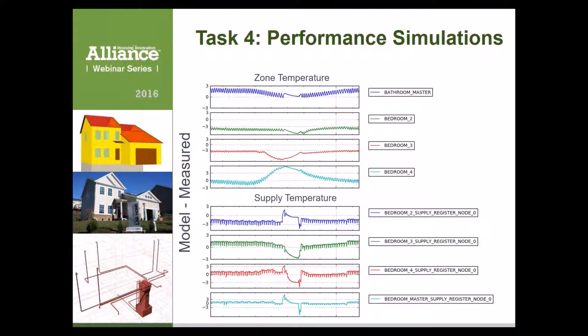A couple of other things we've got in here as well. Have we gone through seasons and various temperature conditions to see if condensation builds up? For example, an unconditioned attic in the winter as heat is pushed through the PVC. One of the benefits of the small diameter is to be able to keep the ductwork within the conditioned envelope — that's a primary objective with this system.